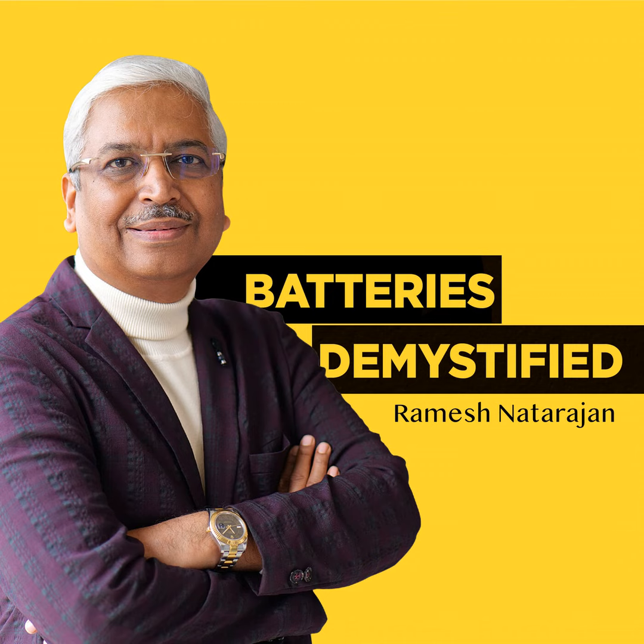Another thing is, these sensors also give audible alarms so that in case the hydrogen level reaches 2 or 3%, the audible alarm can be programmed to come on and you are alerted that the hydrogen levels are going up, so that you can take action before it goes to the 4% concentration.